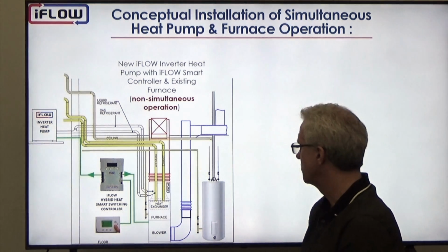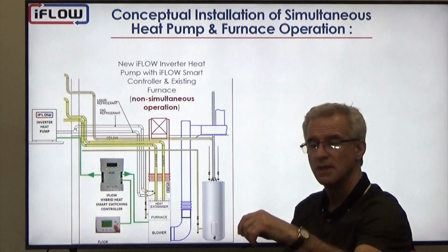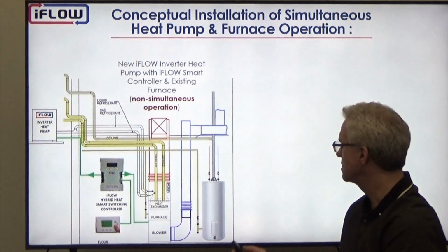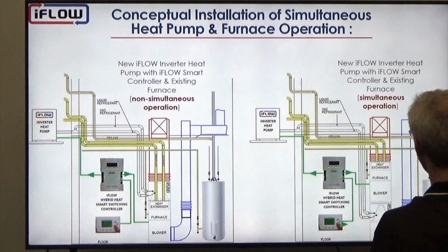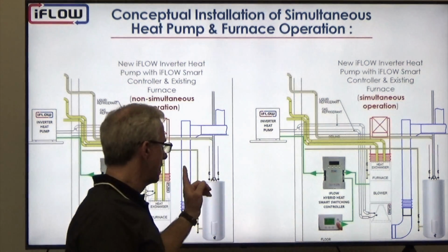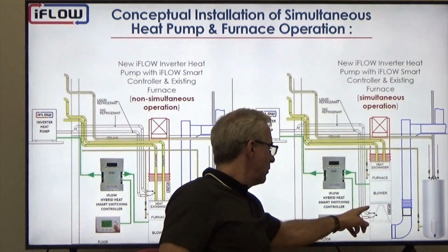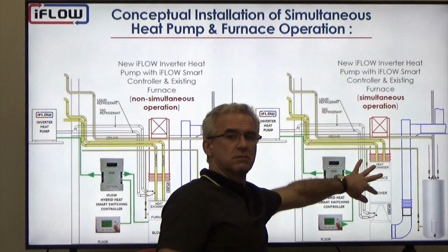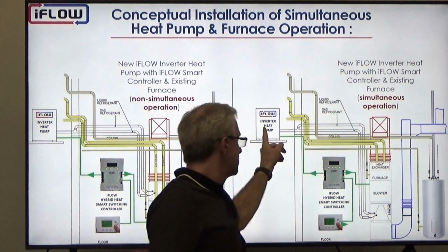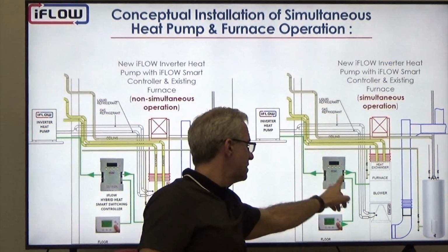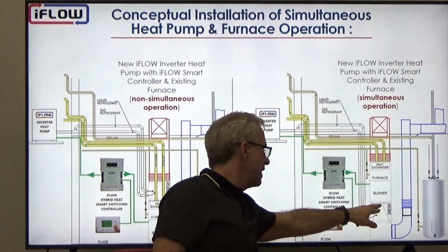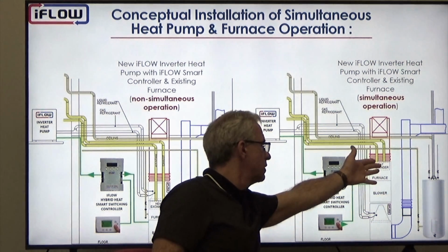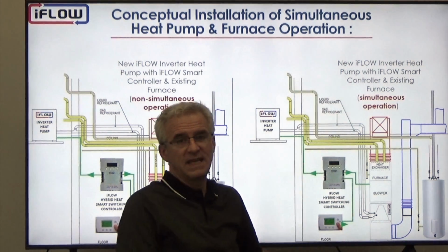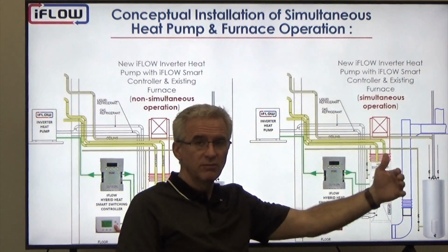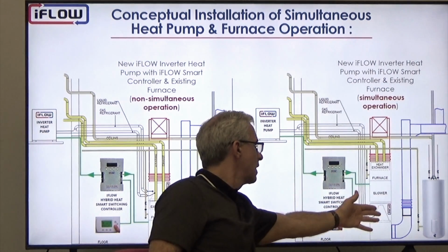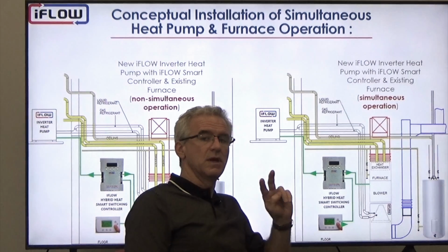This is typical with most of the thermostats out there, because the homeowner will select the method that they want and you can't run them simultaneously. However, with the iFLOW controller, we're going to introduce a new option. In this case, we're going to have the same return, but now we're going to put the evaporator below the furnace. So now we're able to run the heat pump and provide 100% capacity as long as we want into the evaporator. Then that heat goes into the furnace, and the furnace will modulate from there and top up the heat if the heat pump can't provide all of the heating capacity needed for the home. So in this case, we can run both simultaneously.